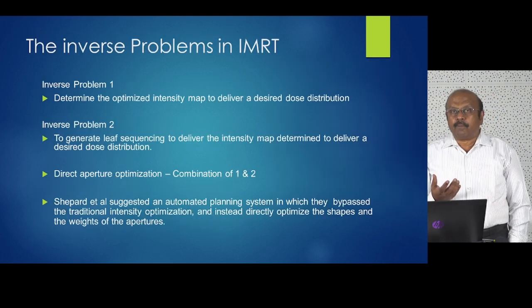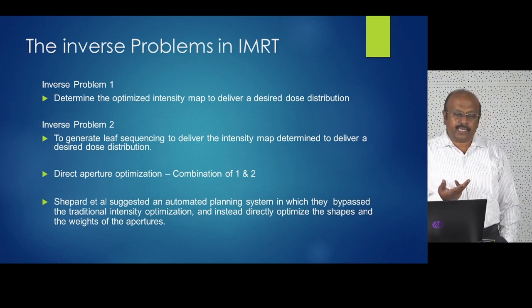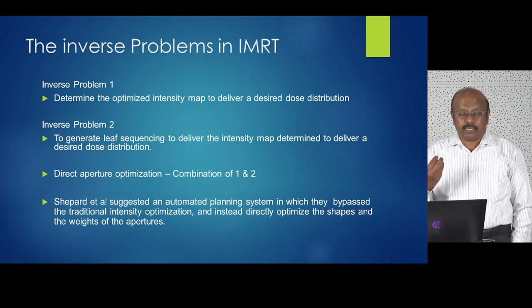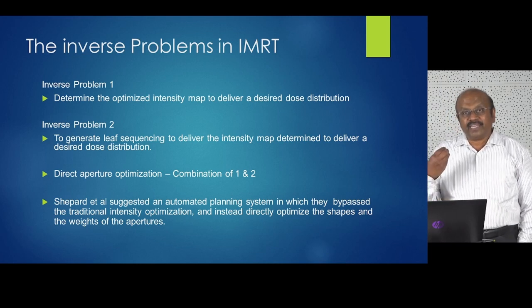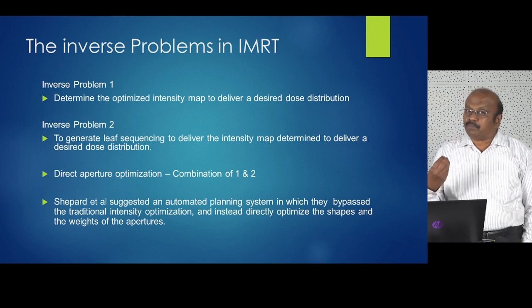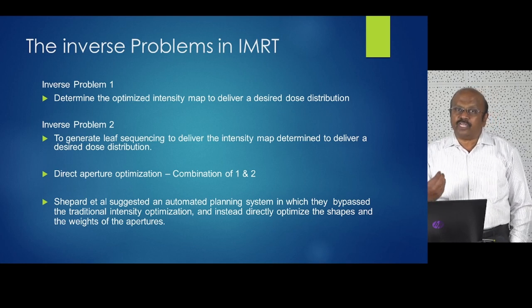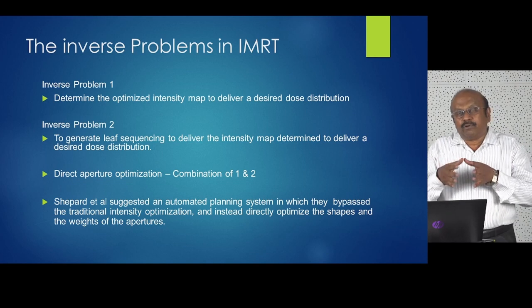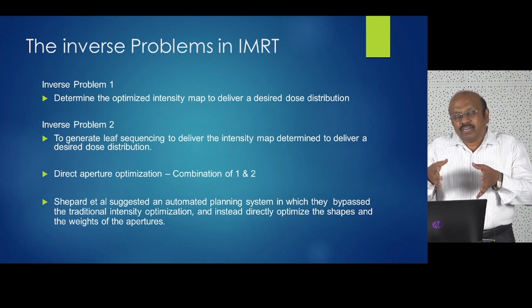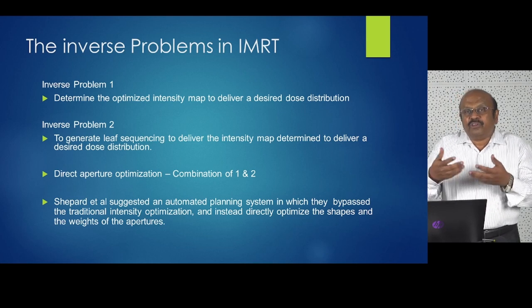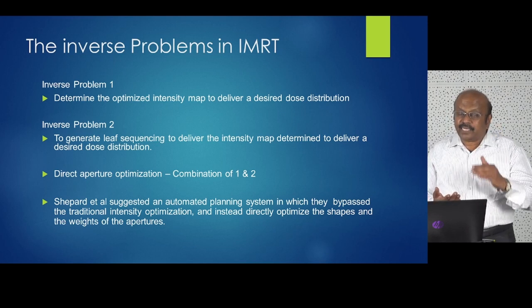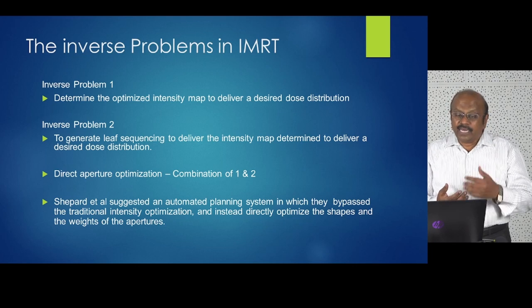There are actually two inverse problems involved in IMRT. The first is to determine the fluence map or intensity modulation depending on tumor location, size, and critical organ position — completely covering the tumor while minimizing dose to critical structures. The second inverse problem is: given that fluence, how must the leaves move to deliver it? You have to arrive at a leaf sequence. In most current planning systems, including VMAT, these two inverse problems are combined — called direct aperture optimization.